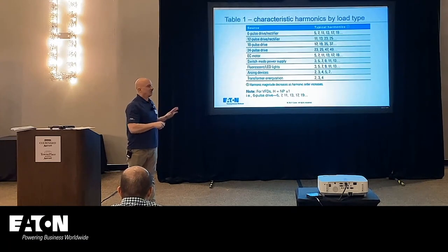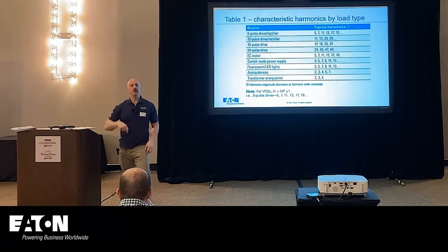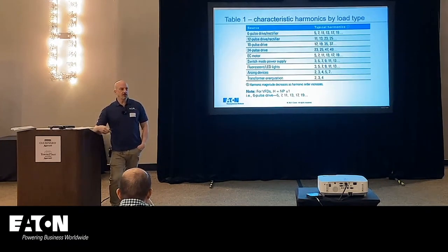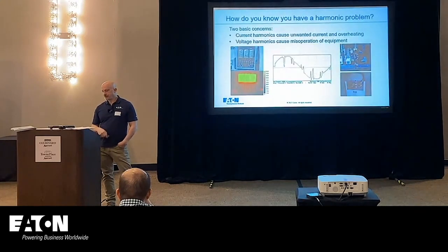But even harmonics, if you looked at the top half of the waveform and the bottom half of the waveform, even harmonics are not the same. Odd harmonics, the top half of the waveform and the bottom half are exactly the same, or symmetrical, okay? So even harmonics are an indication of something different than normal. When you energize a transformer and you hear that dong, it doesn't last forever, does it? It's only there for a little bit. Arcing devices like steel mills, arc furnaces, stuff like that, that can be short term, but it's not usually consistent for a long period of time.